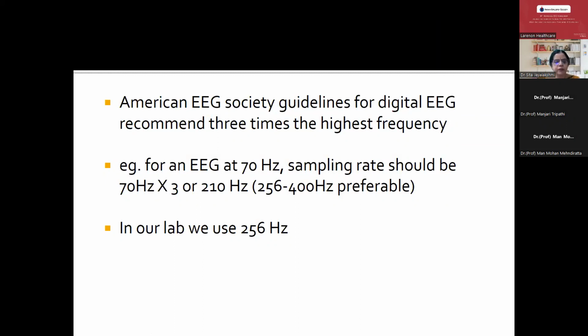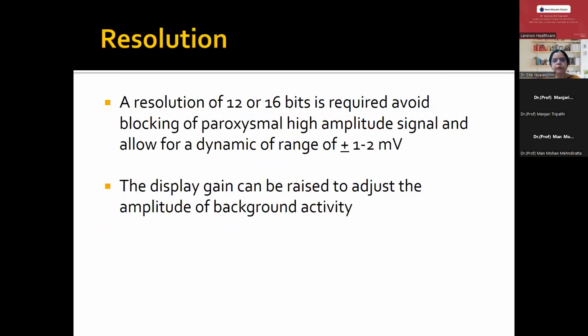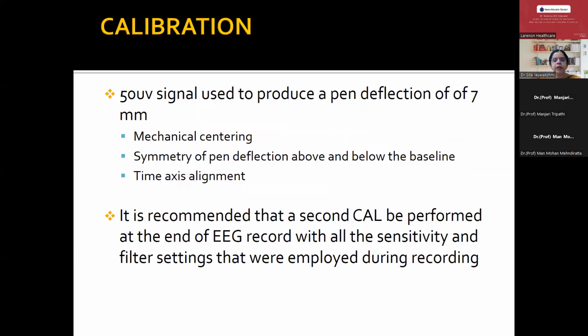But nowadays with SEEG recordings, we use very high sampling rates, almost up to 1000 hertz. Then the resolution of the monitor is also important. It should be around 12 to 16 bits to avoid blocking of paroxysmally high amplitude signals. Once we know how the signals are coming, we start recording on the digital machine, and whenever we start recording, the most important thing is calibration.